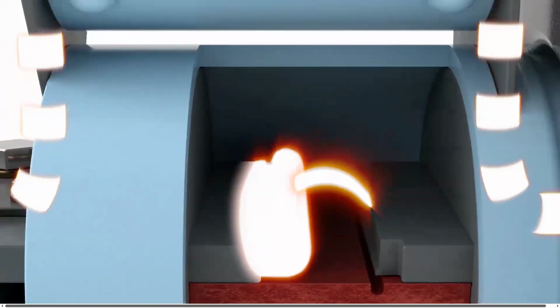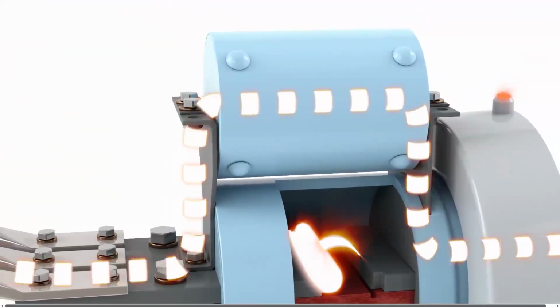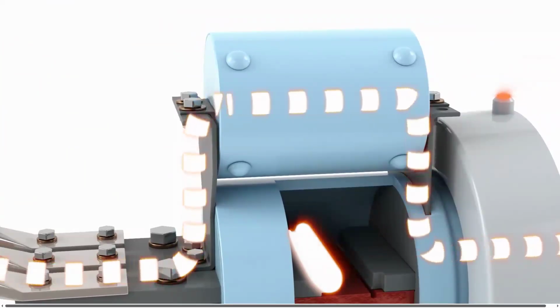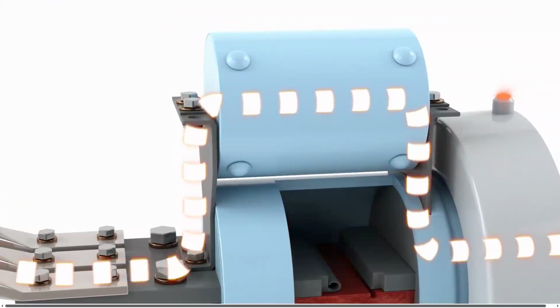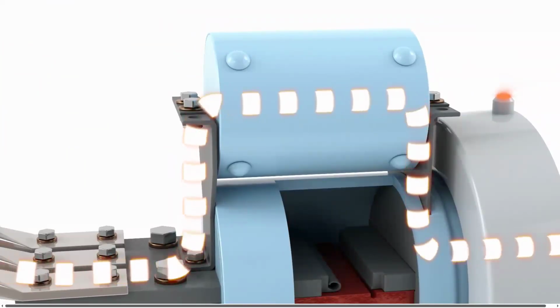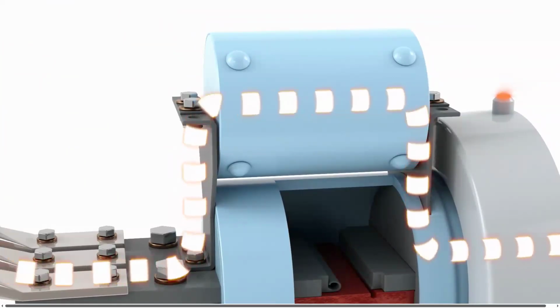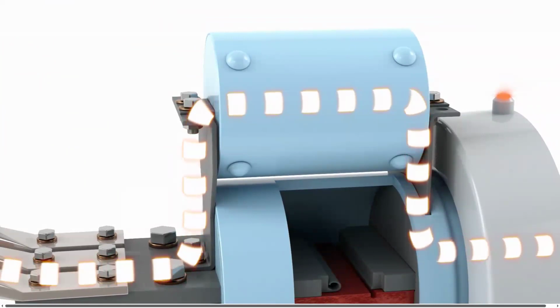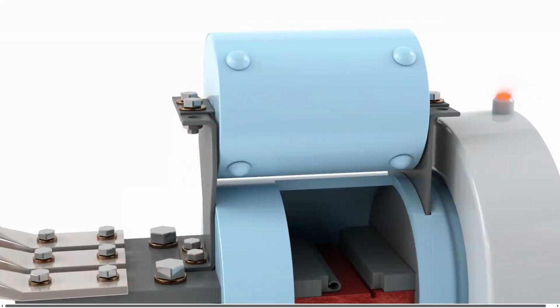current limiting fuse. During the time it takes the fuse to melt, the gap recovers dielectrically and the arc ceases to exist. The fuse completes its melt and clears the circuit, just like a conventional current limiting fuse. When the fuse opens, the current flow is quickly reduced to a low level and then fully extinguished at or before the first current zero point. This occurs at 1/4 cycle on a purely symmetrical fault, protecting the equipment and minimizing personnel's exposure to hazards.